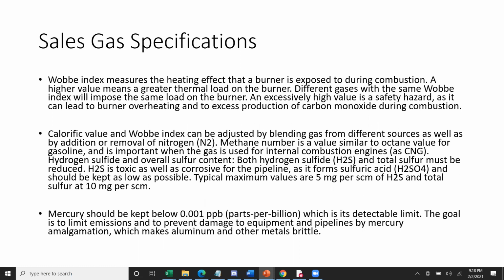The Wobbe index measures the heating effect that a burner is exposed to during combustion. A higher value means a greater thermal load on the burner. Different gases with the same Wobbe index will impose the same load on the burner, and an excessively high value is a safety hazard, as it can lead to burner overheating and excess production of carbon monoxide during combustion. Calorific value and Wobbe index can be adjusted by blending gas from different sources, as well as addition or removal of nitrogen. The methane number is a value similar to the octane value for gasoline, and it's important when gas is used for internal combustion engines, such as compressed natural gas.